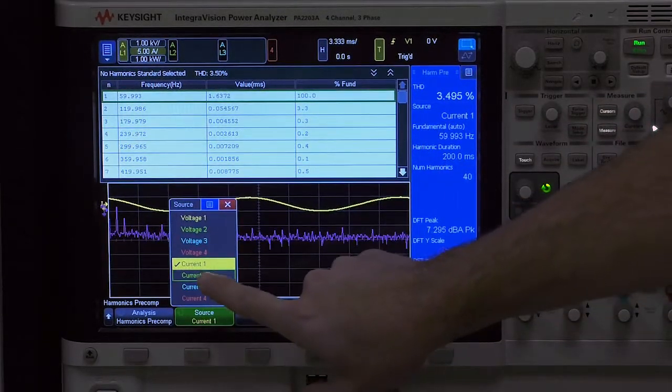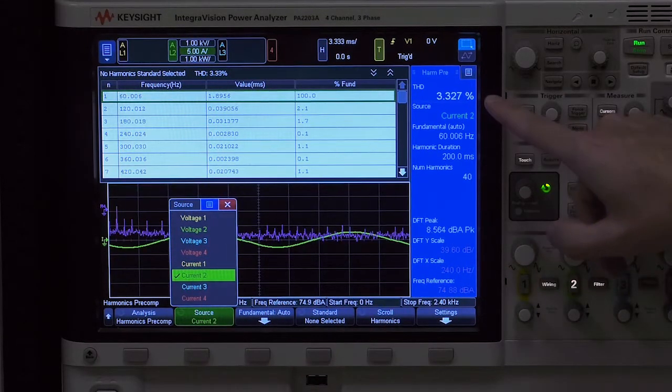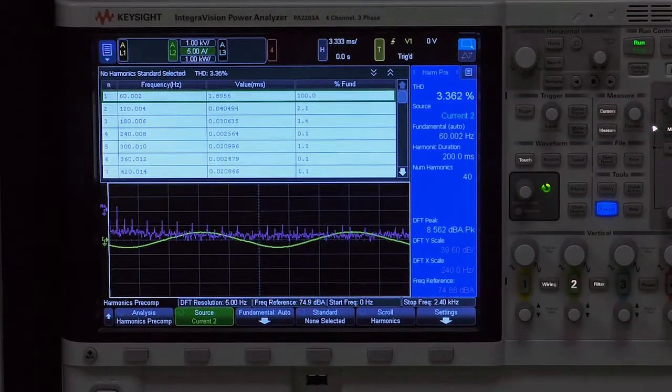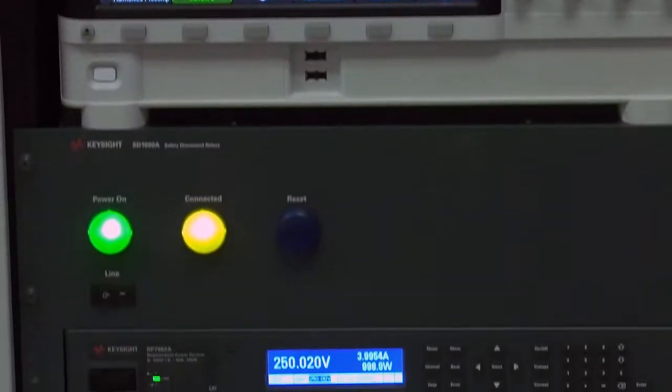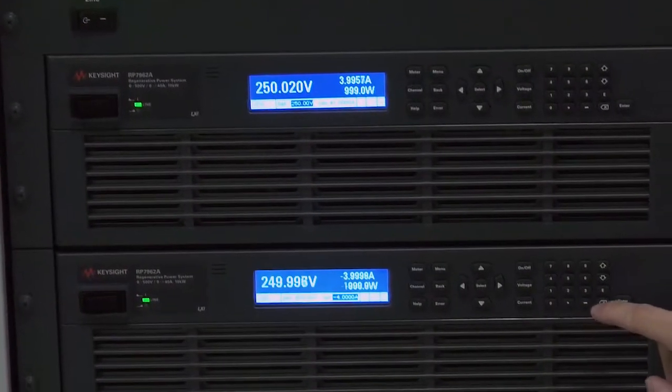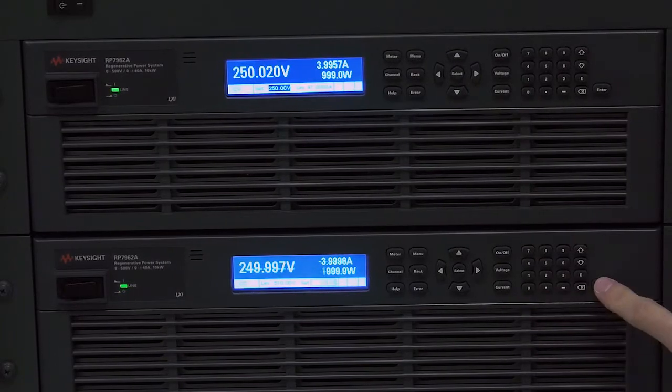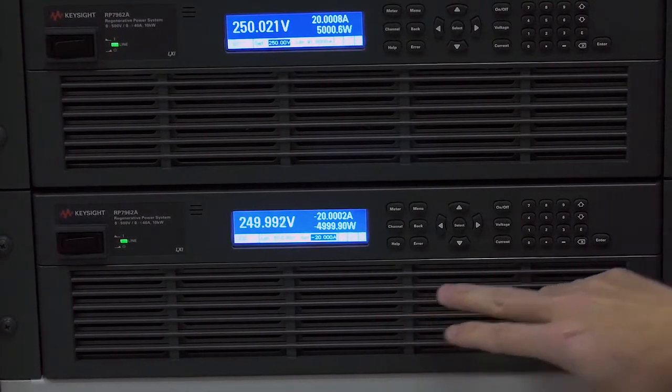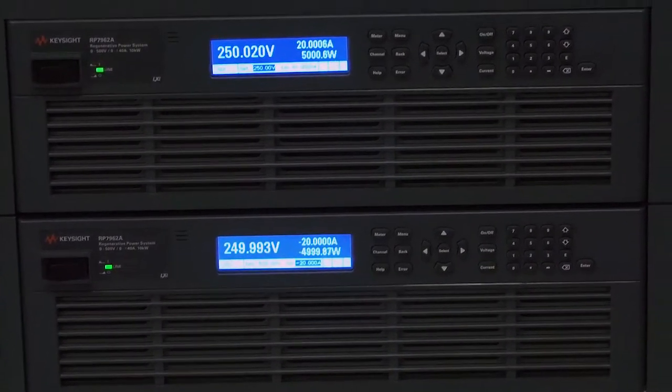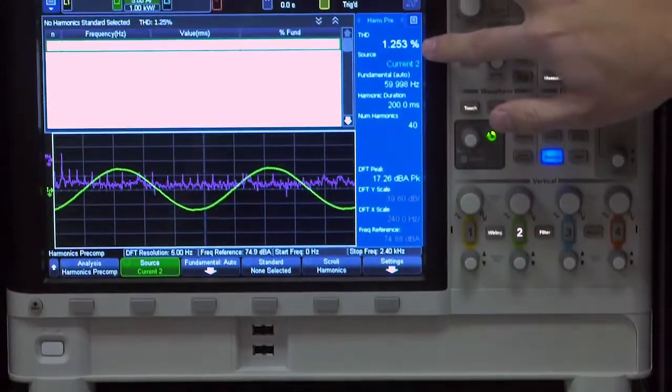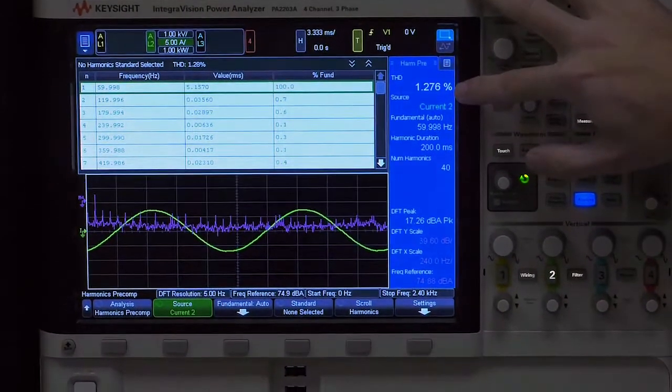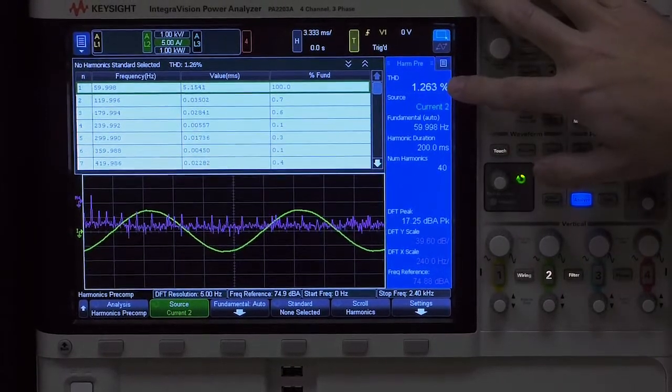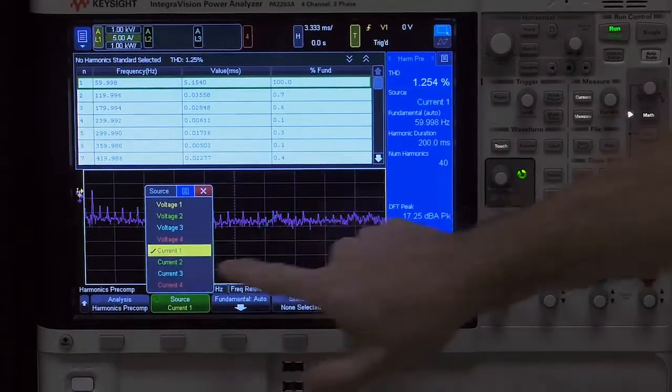Now if you take a look at another phase, the current of phase two, you can see the measurement is roughly the same, 3.3 percent. Okay, so that was 1000 watts. Let's go up to 5000 watts by changing that to 20 amps. So now we're sinking 250 volts, 20 amps DC back to the grid. And you can see that actually at higher powers the cleanliness is better. The total harmonic distortion goes down from three and a half percent to 1.2 percent. And again, we can look at the current of phase one. It's actually even better, about one percent total harmonic distortion. Let's look at phase three.